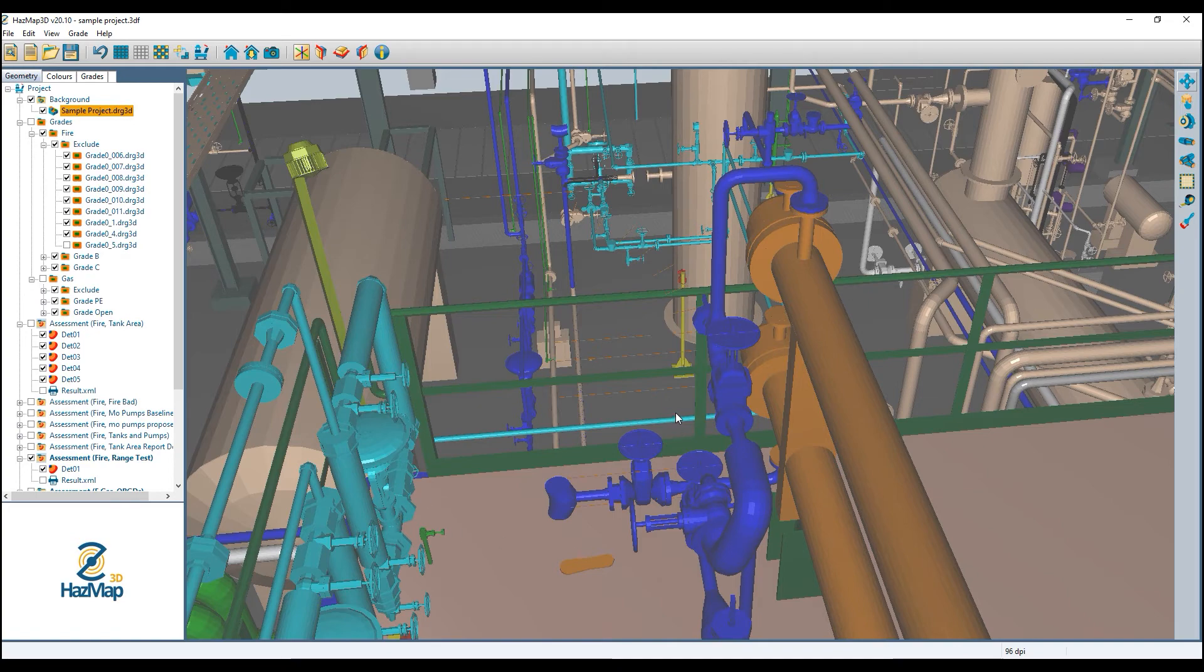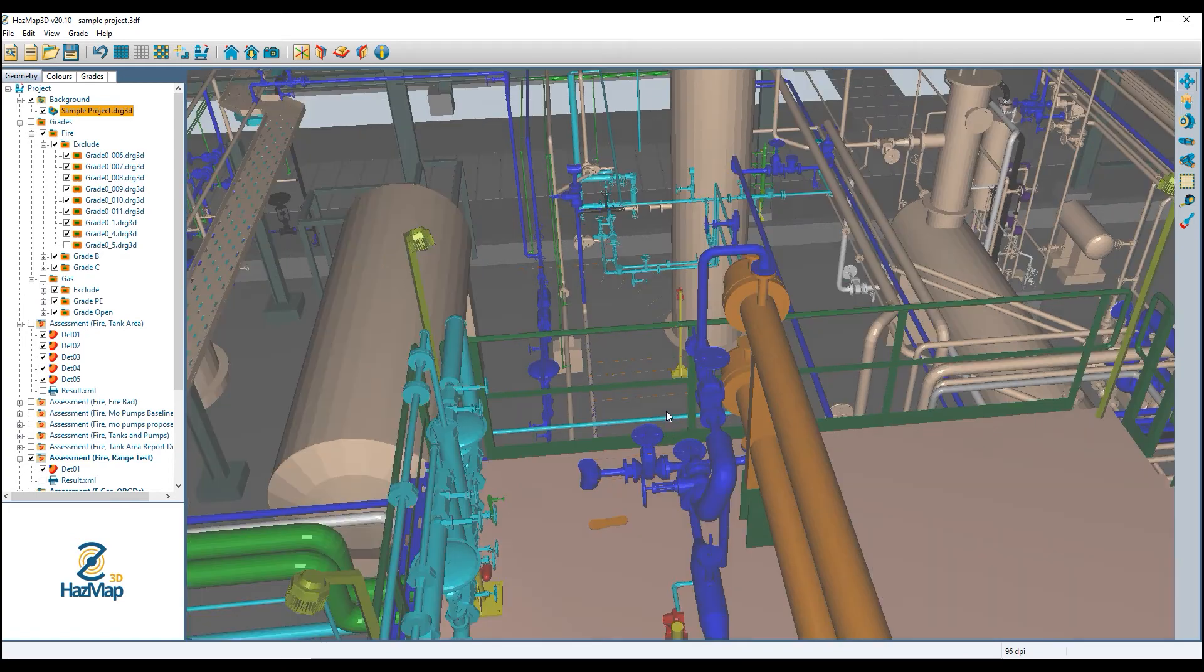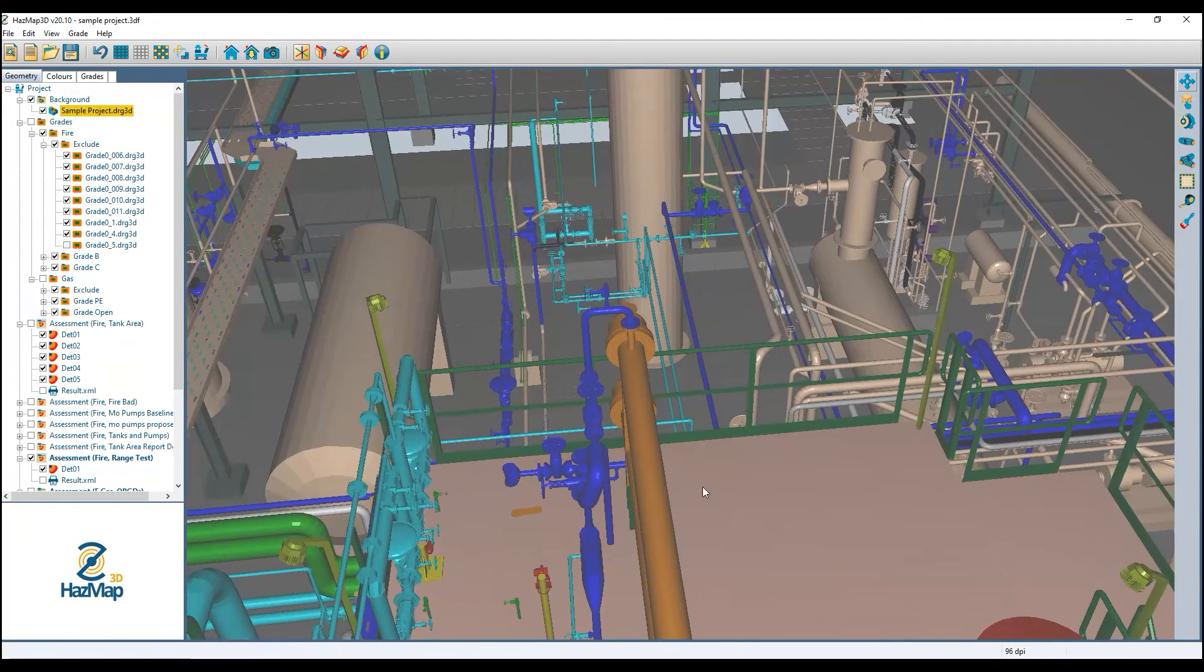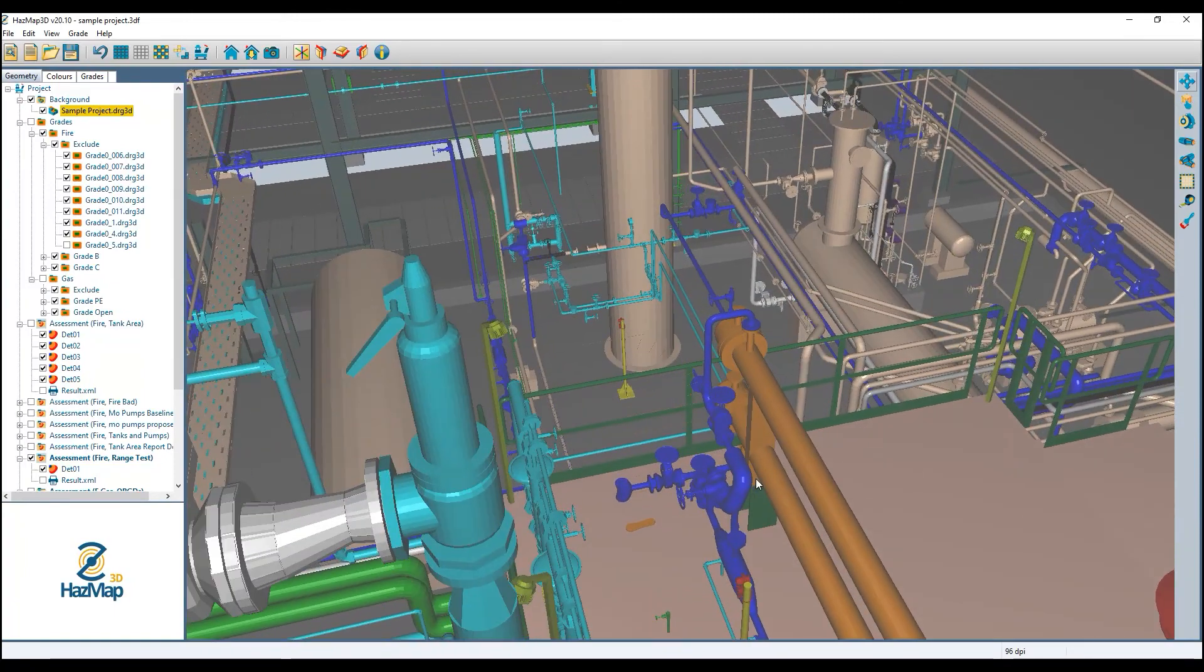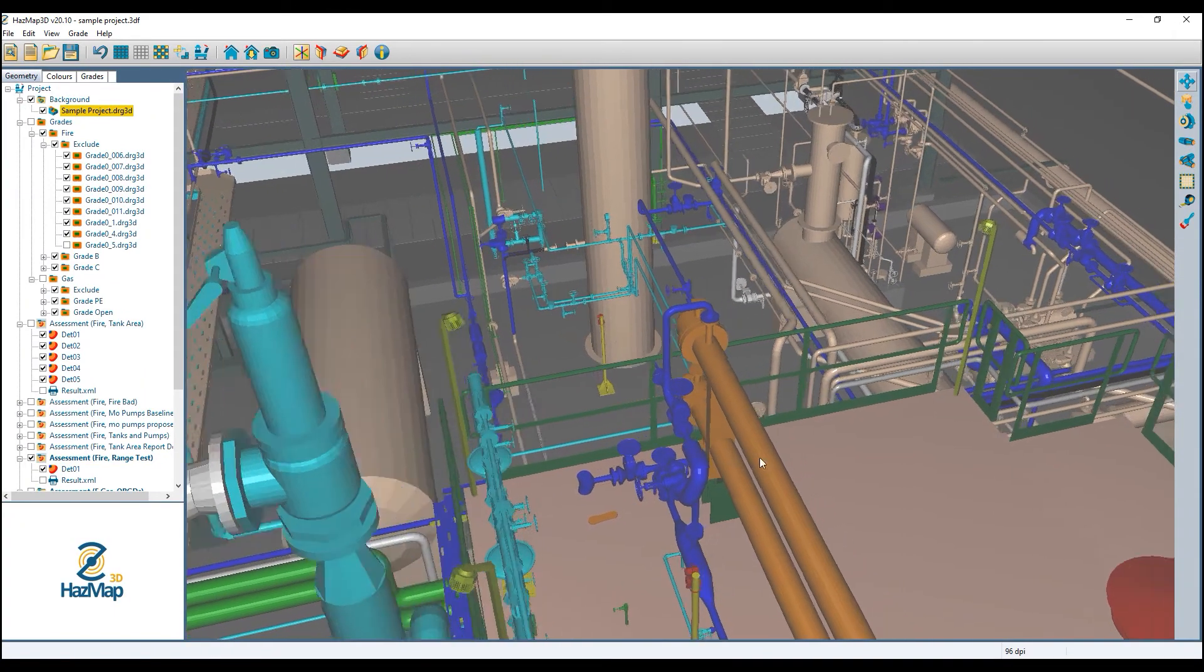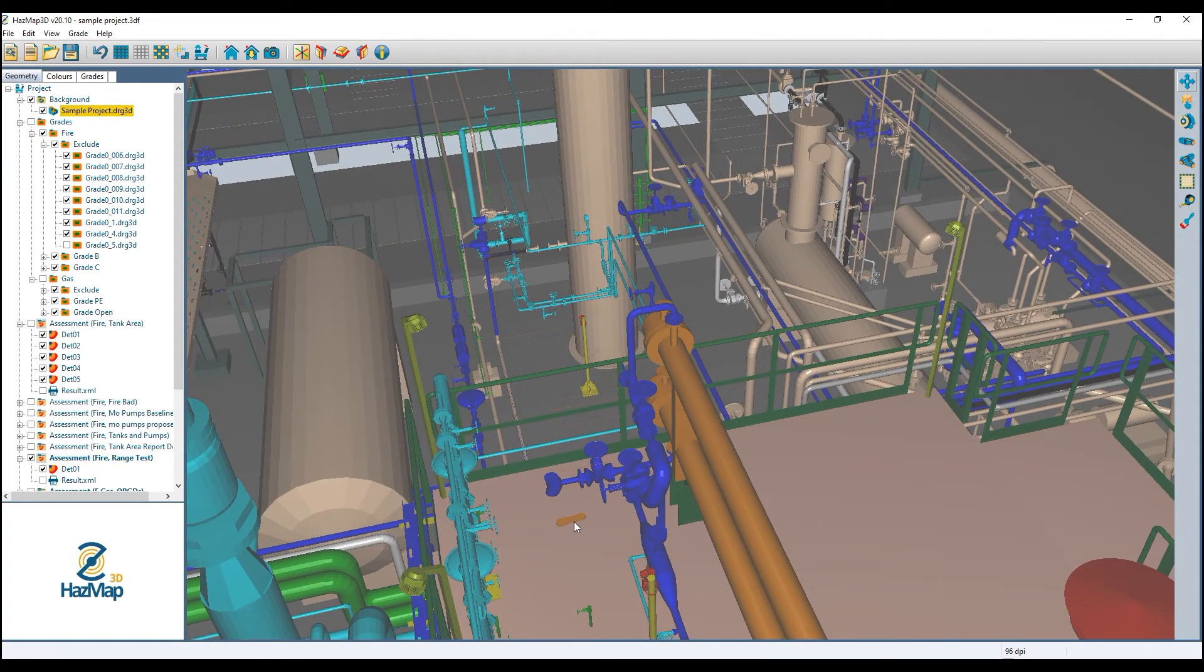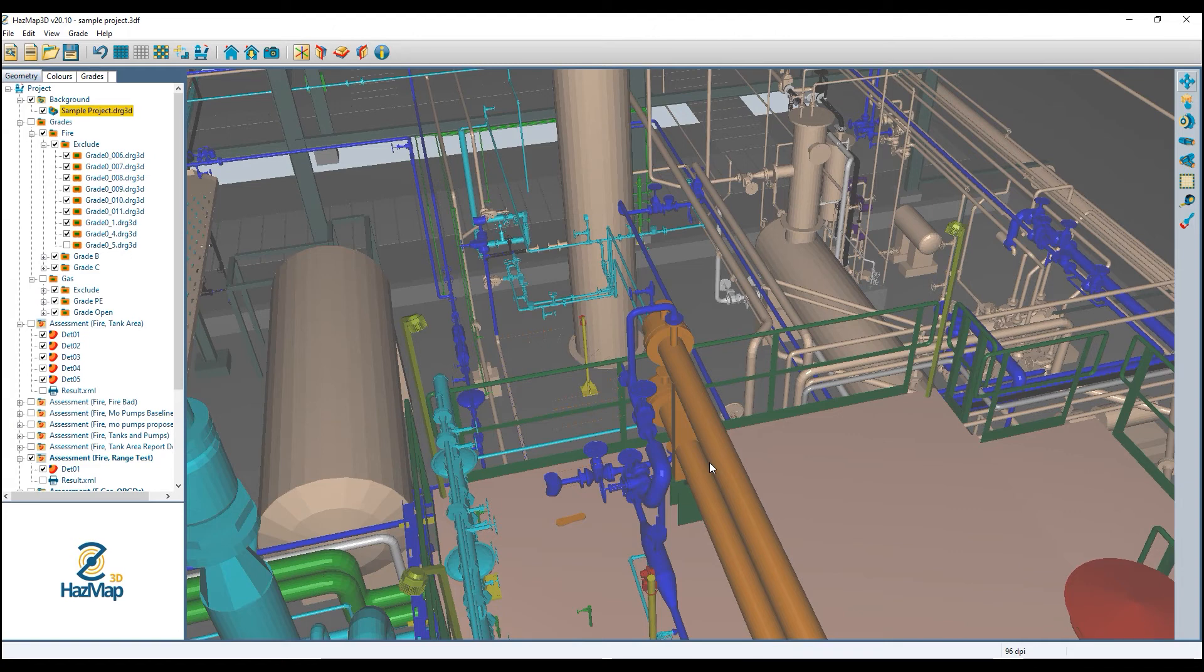The main reason for deleting these objects from the model is that HazMap3D cannot differentiate between a temporary object like that 3D worker and a permanent fixed object. It will treat all of it like an obstruction for flame detection.